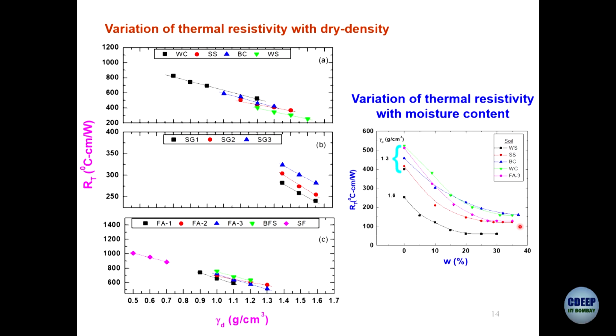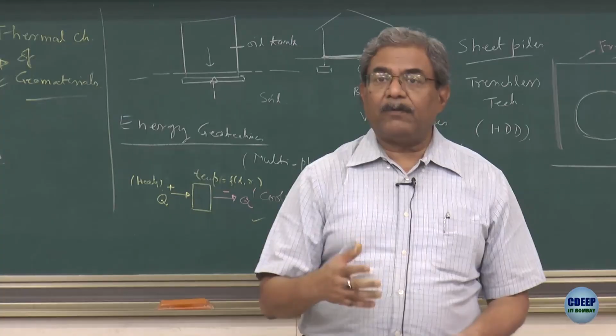What does water do when you add water to these types of soils? As the moisture content increases, the resistivity decreases. This is what we actually discussed, because all the pores are now filled up with water, and water has the least thermal resistance as compared to air. So, ultimately the entire characteristic converges to the thermal resistivity of water. So, saturated soils will show you the minimum possible resistivity as compared to the driest state of the soil. So, when you talk about material characterization, these types of nomograms become very handy.